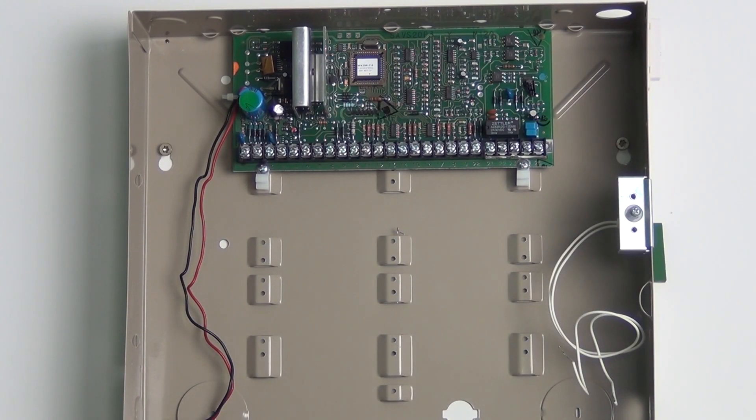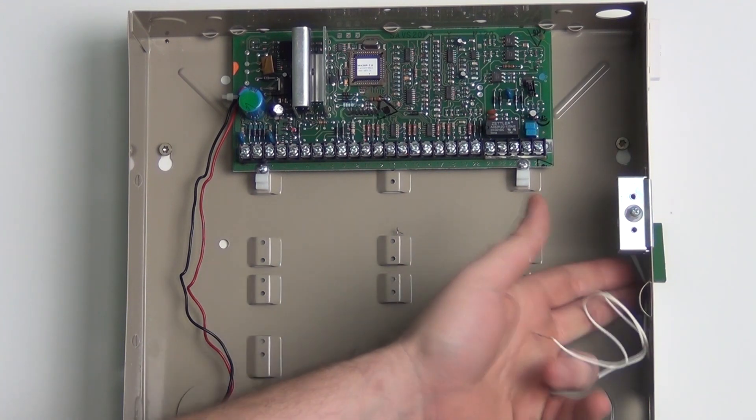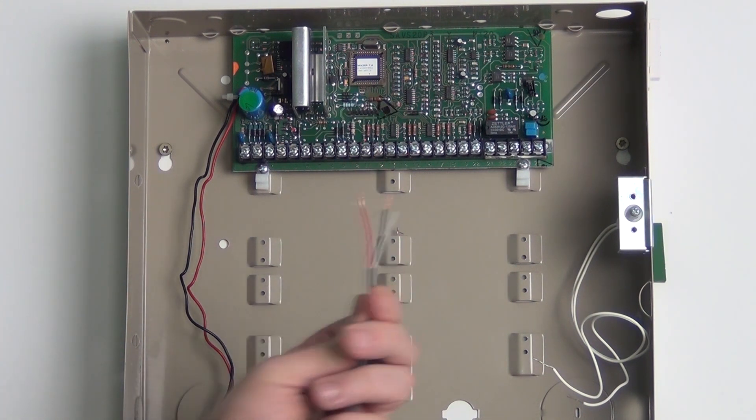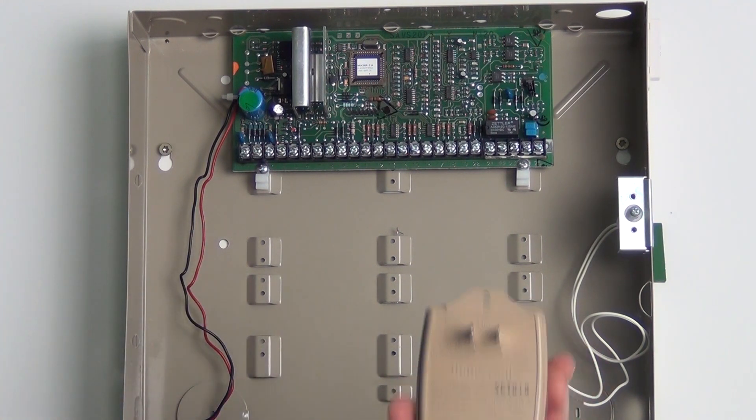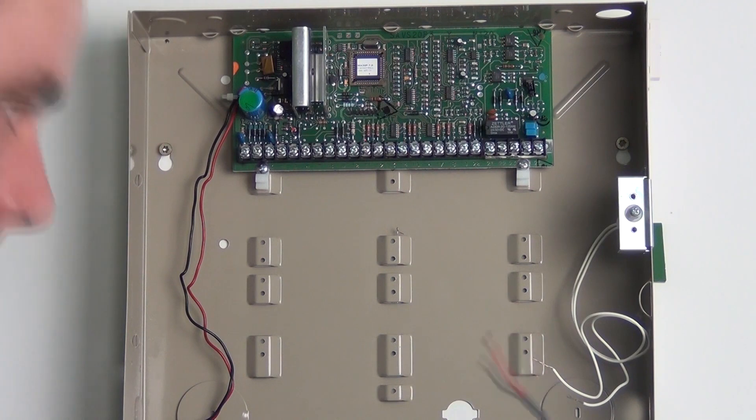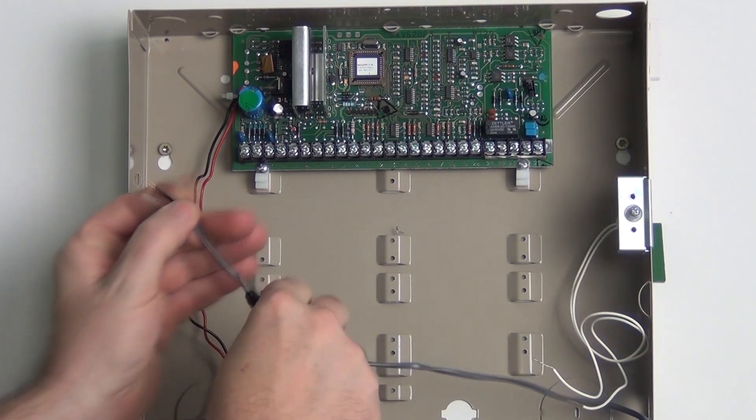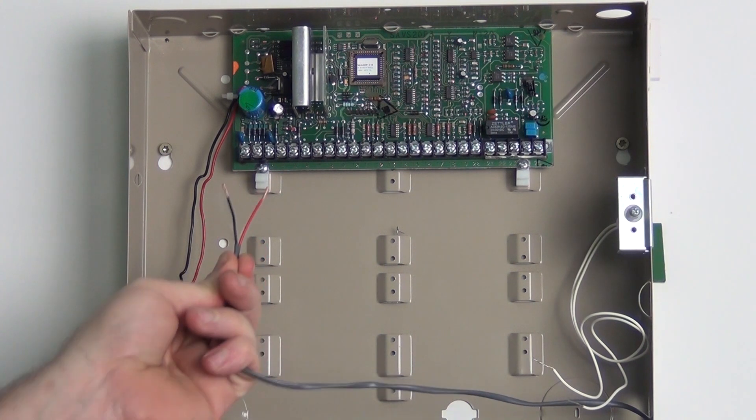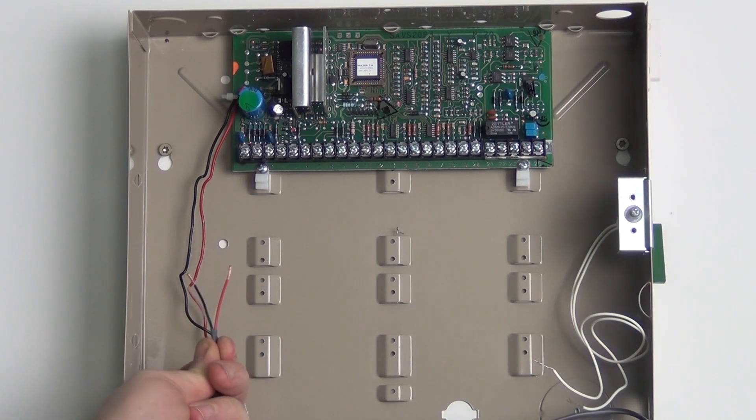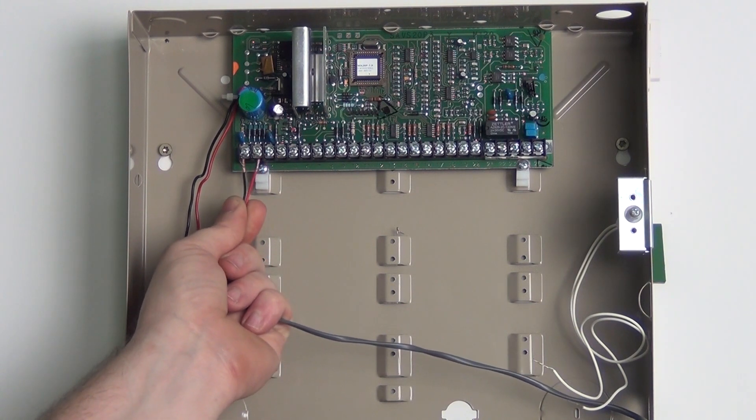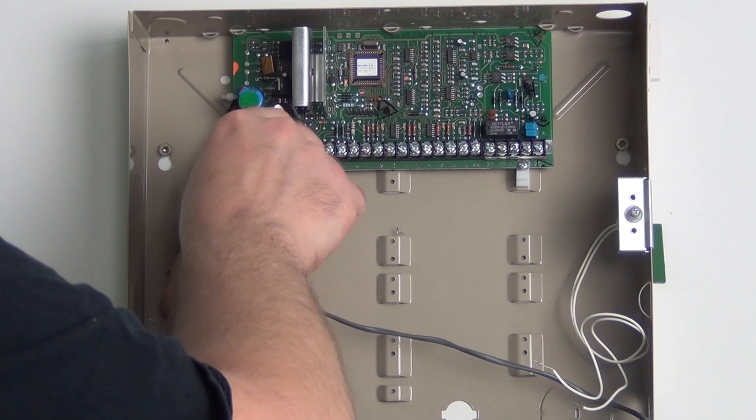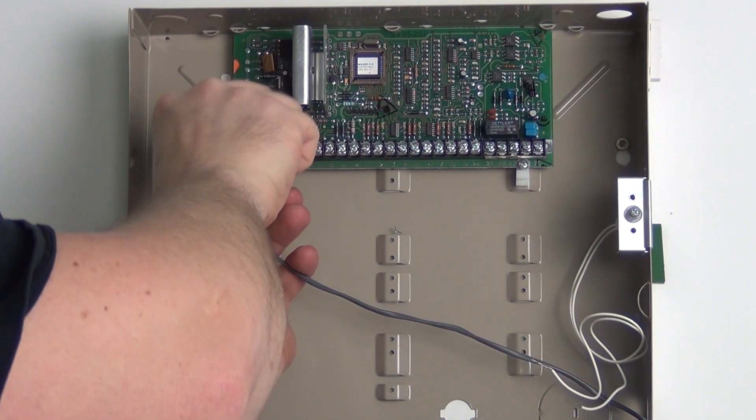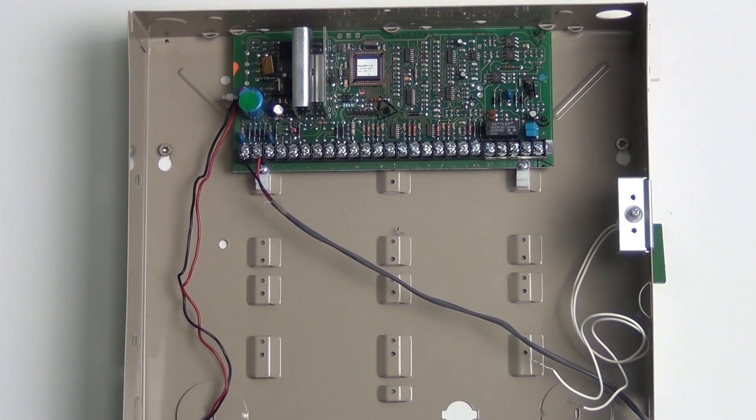Here we are at the Vista 20P panel on the wall. I've got the door off and I've stripped it down so you can see what it looks like. The first thing I'm going to do is hook up the power transformer. I've got these two wires running down to a Honeywell transformer. I'm going to run them through the knockout hole and bring them to terminals 1 and 2 on the board. On a Honeywell Vista panel there is no polarity, so you can wire the black and red to whatever terminals you want. I'll stick these wires under the screw terminals and tighten them down. Don't over-tighten these screws because you will strip them out, just make sure they're nice and snug.